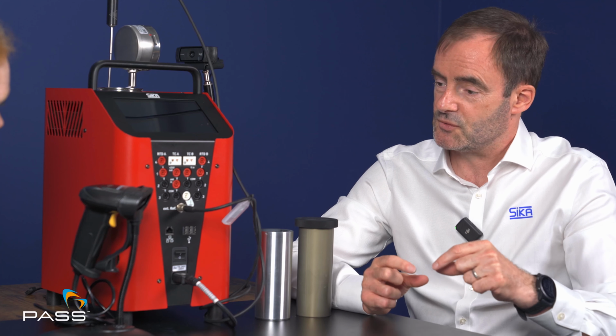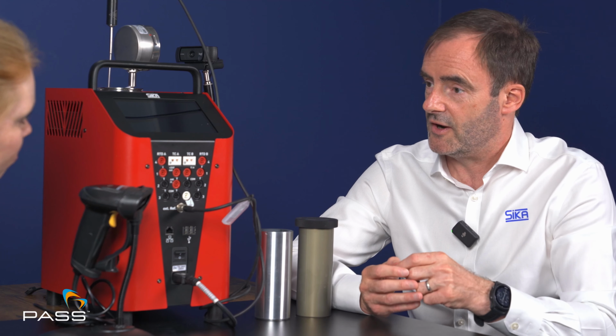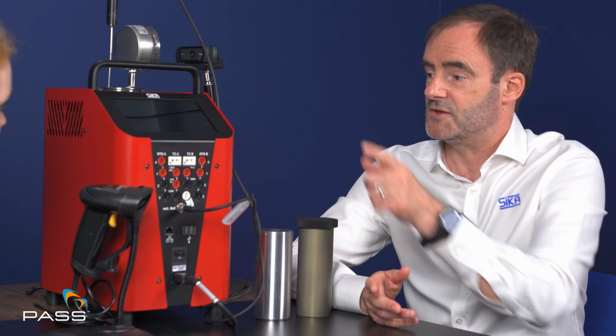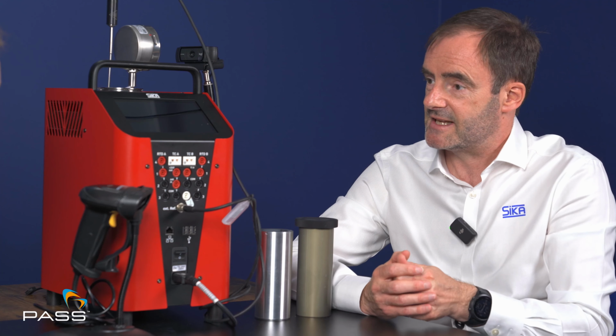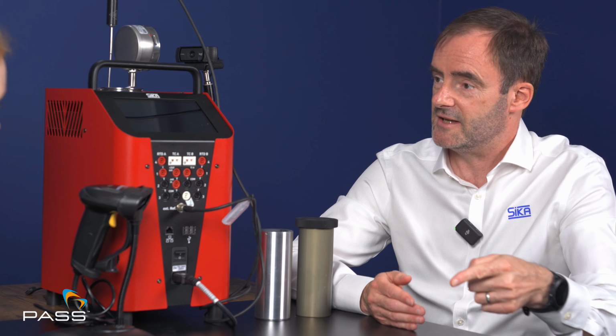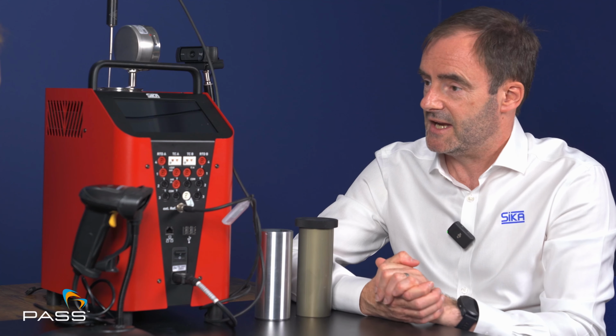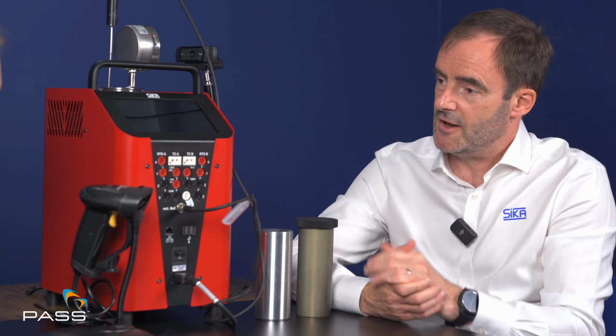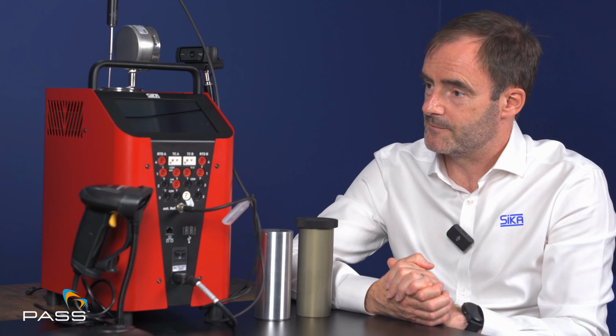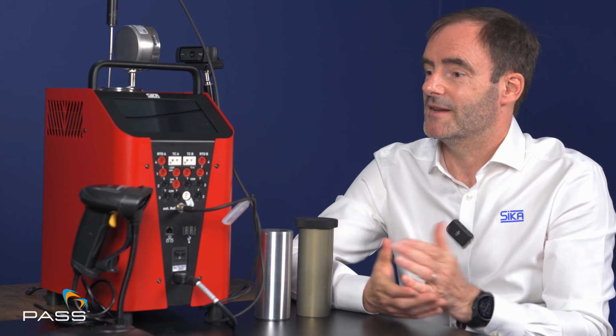A lot of customers tend to have a number of different temperature sensors that look the same, so you may want to have an actual barcode for each device. When you've set up that device within the unit, you can scan it the next time you come to calibrate it, and the calibrator will remember the data and pick it out, so you'll be able to calibrate more quickly. That really plays into convenience and efficiency, doesn't it?